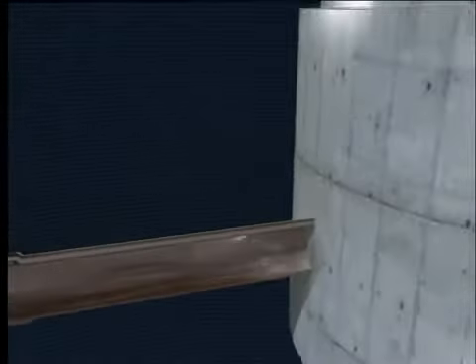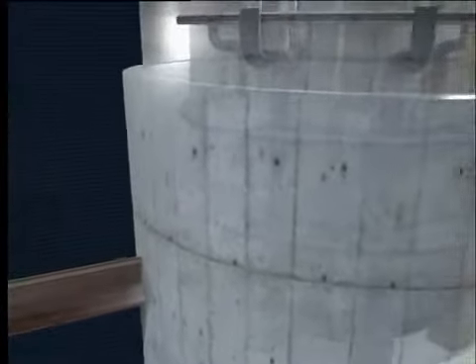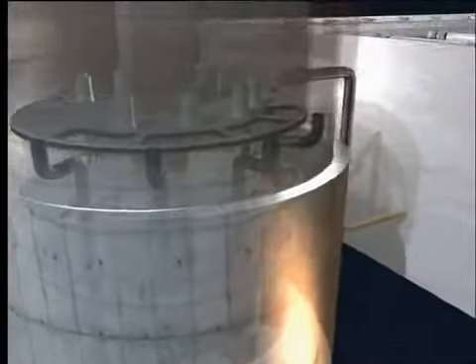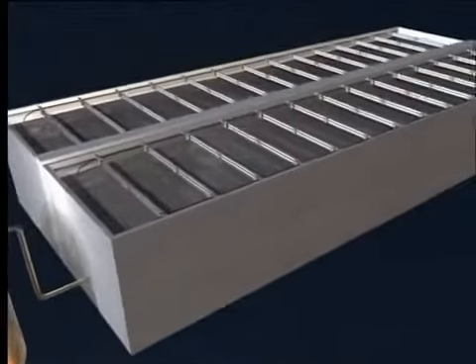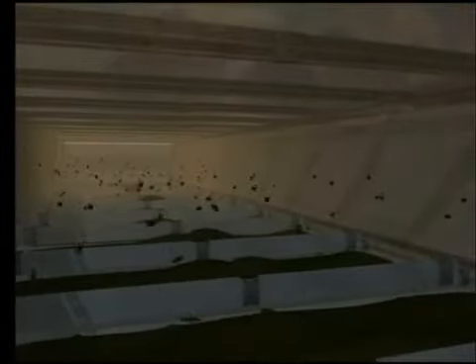Once the sewage arrives at the plant, it is lifted to the sedimentation tanks by pumps housed in the main pumping station, which is one of the world's largest underground sewage pumping stations. The sewage then undergoes a process of enhanced primary sedimentation involving the application of a chemical treatment. The objective during this stage is to enhance the removal of suspended solids and biological oxygen demand in the sedimentation by using a chemical, ferric chloride, and a polymer to quicken the sedimentation process.